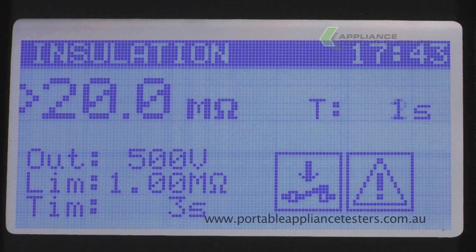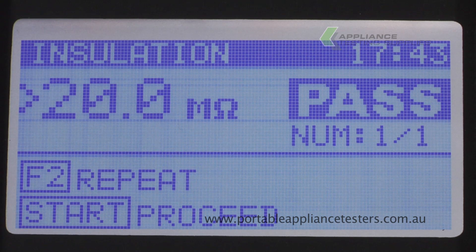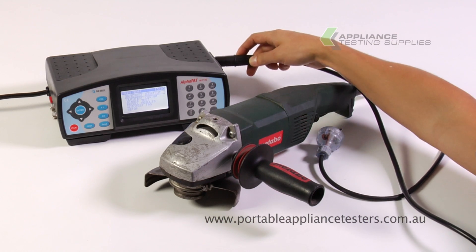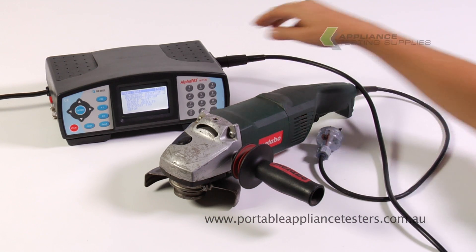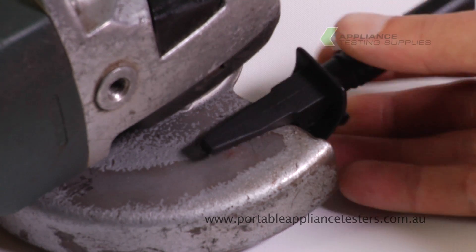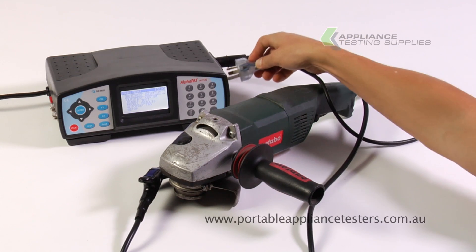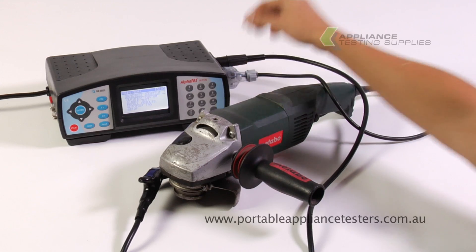Pass or fail is indicated when the test is complete. Testing class one equipment. Plug the earth bond lead into the side of the appliance tester. Using the crocodile clip, attach it to the exposed metal part of the item under test. Plug the item into the side of the appliance tester and switch it on.